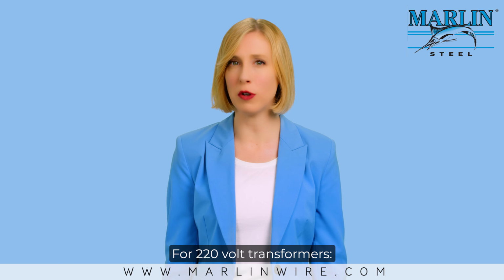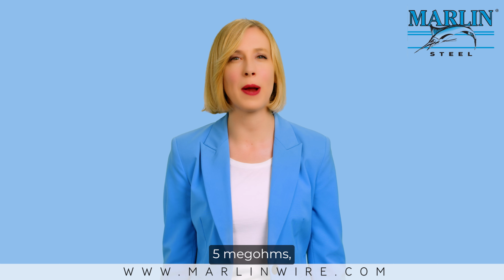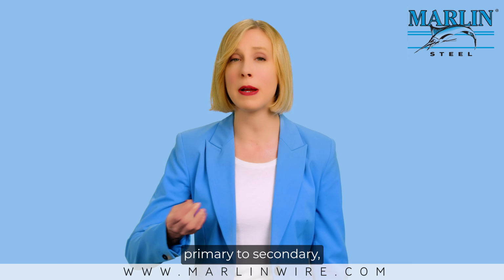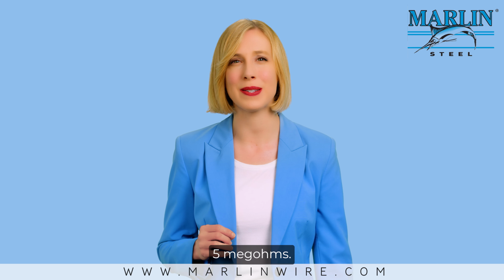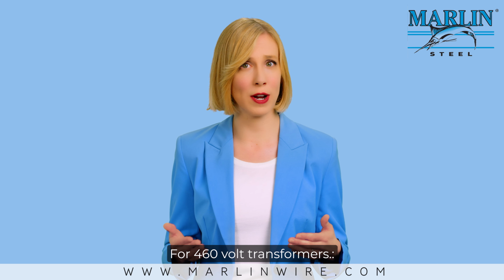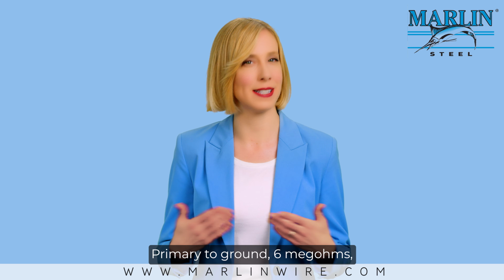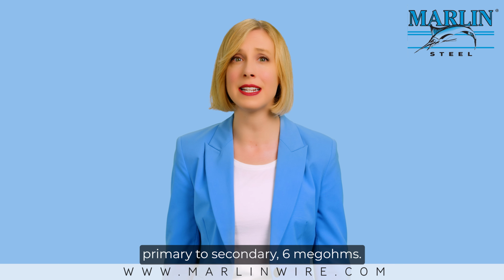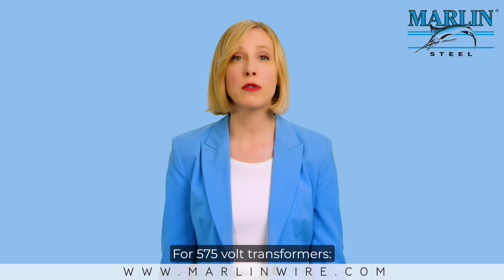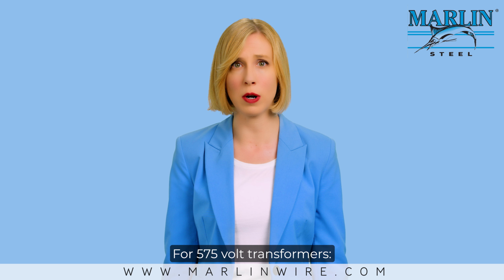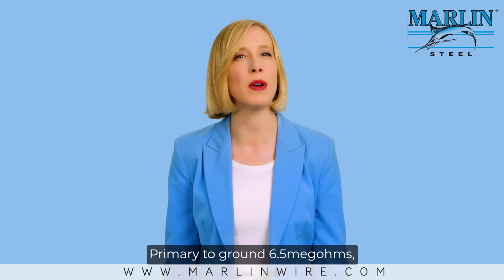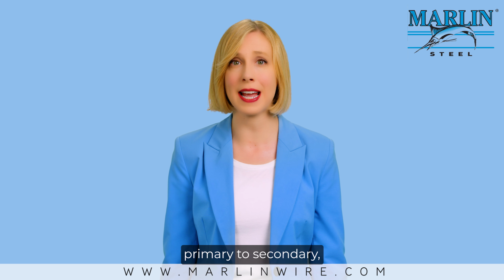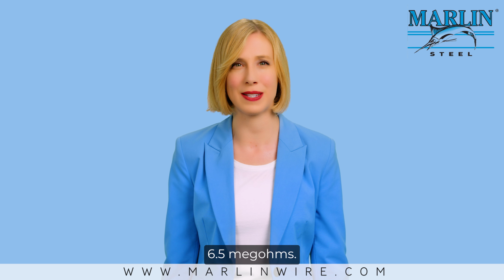For 220 volt transformers, primary to ground 5 megohms, primary to secondary 5 megohms. For 460 volt transformers, primary to ground 6 megohms, primary to secondary 6 megohms. For 575 volt transformers, primary to ground 6.5 megohms, primary to secondary 6.5 megohms.